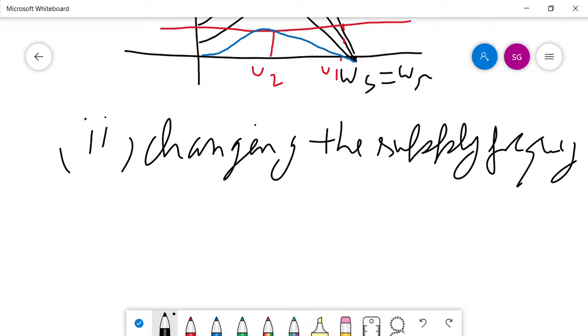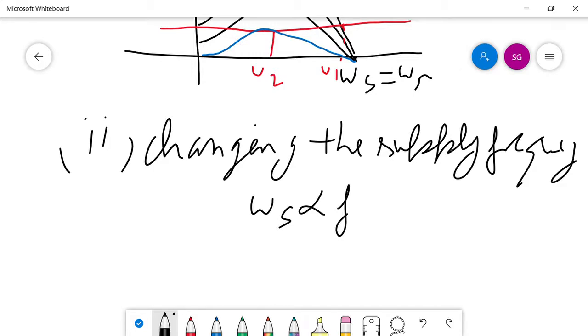The synchronous speed of the stator-generated magnetic field will change. As we know, omega_s is directly proportional to supply frequency. So if we decrease this frequency, our omega_s point will change — the point at which the slip was zero will shift. It is like shifting the DC motor characteristic by changing the field. We can draw a new torque-slip characteristic.